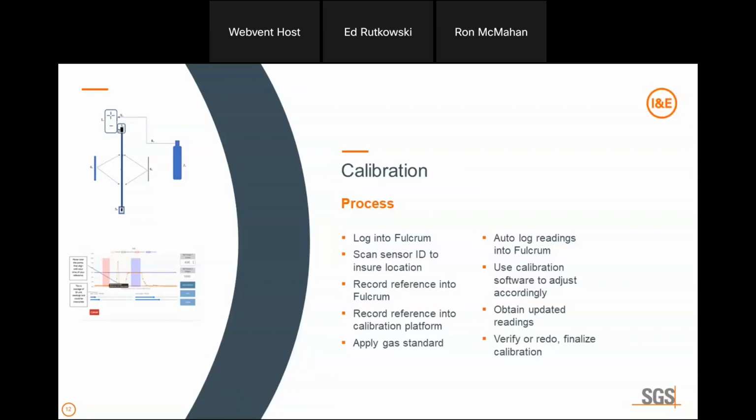Again, there may be some drift or some small changes, but in indoor environments, typically you don't have very aggressive sensor drift or changes. And so it's very useful to be able to compare that data now to where we were. In the process with the university in Boston, we're working with them to actually be able to back calculate that and provide 2 data sets. One that says, here's what it was, and one that says, here's the corrected data based on our latest calibration. Both of them will be public, both will be available.